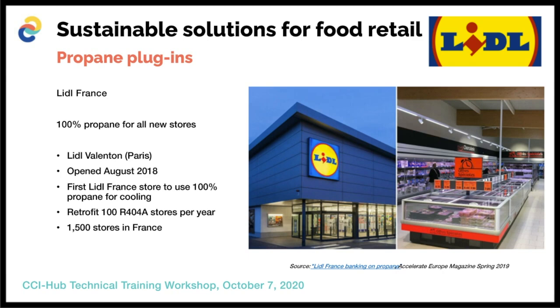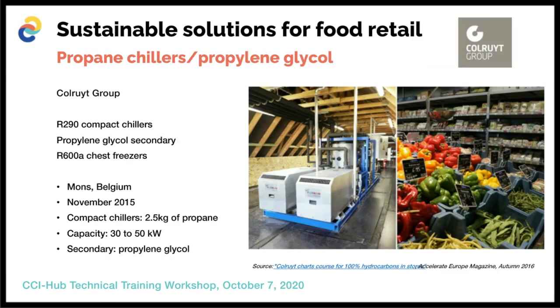Next example, another use of propane in commercial refrigeration comes from Belgium. A Colruyt group is using propane chillers with glycol as a secondary coolant that is then circulated in the showcases to cool all, or most, I believe, of their supermarkets in Belgium. They also use plug-in hydrocarbon systems, and lately they have also installed a hydrocarbon heat pump on their roof to provide air conditioning. So you see that there is a lot of innovation in this space.